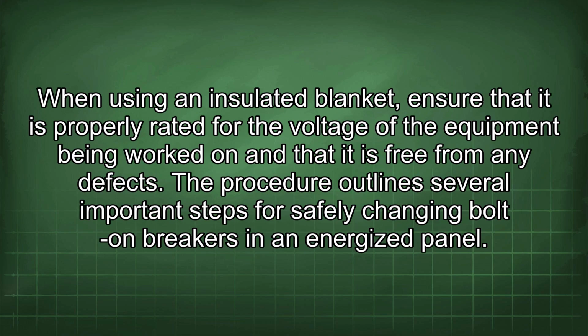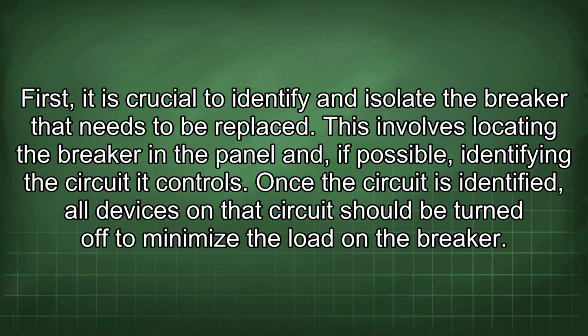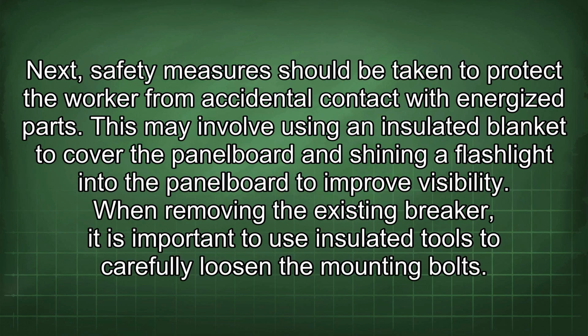The procedure outlines several important steps for safely changing bolt-on breakers in an energized panel. First, it is crucial to identify and isolate the breaker that needs to be replaced. This involves locating the breaker in the panel and, if possible, identifying the circuit it controls. Once the circuit is identified, all devices on that circuit should be turned off to minimize the load on the breaker. Next, safety measures should be taken to protect the worker from accidental contact with energized parts. This may involve using an insulated blanket to cover the panel board and shining a flashlight into the panel board to improve visibility.